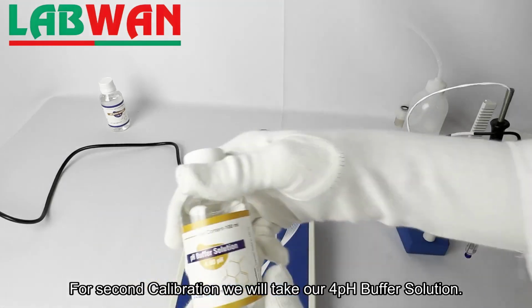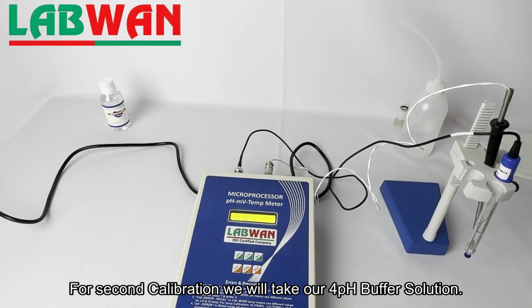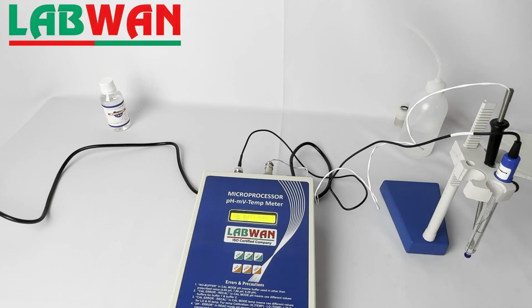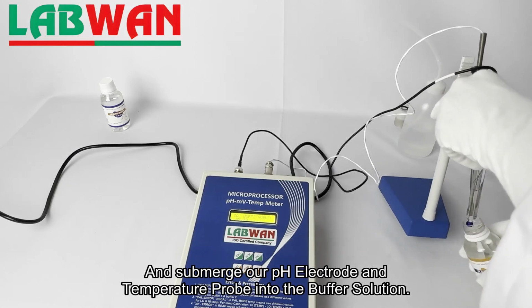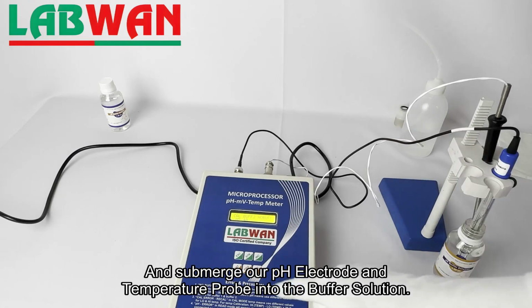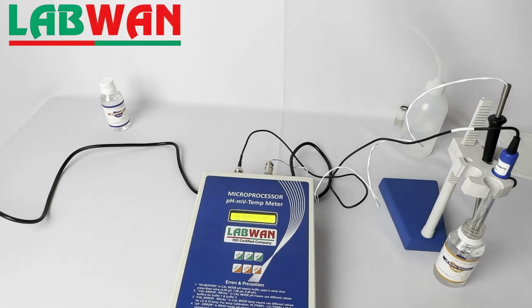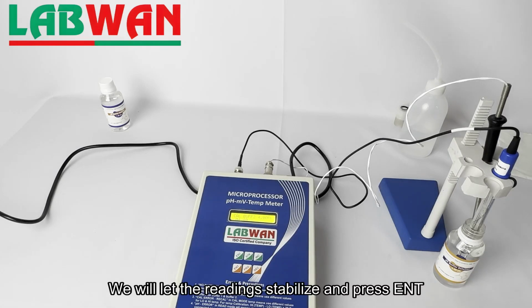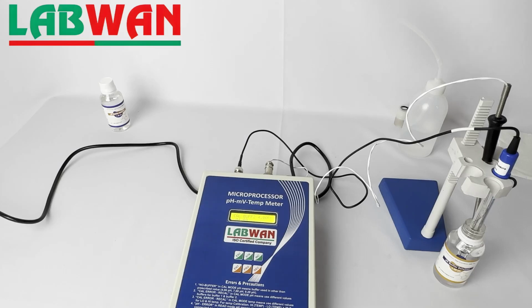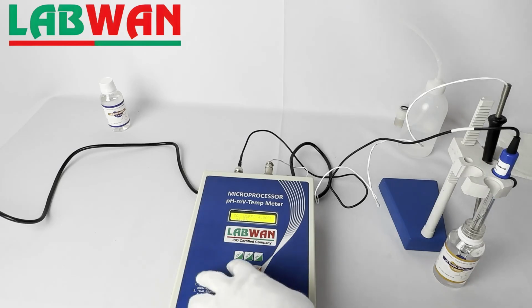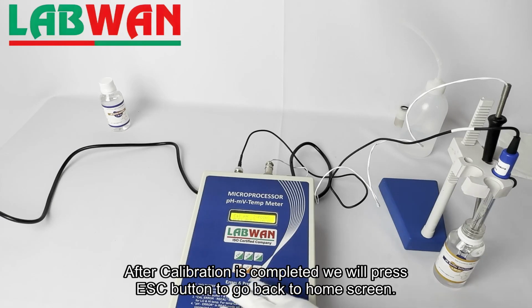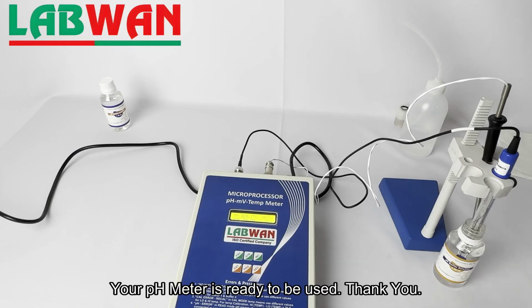For second calibration we will take our 4 pH buffer solution and submerge our pH electrode and temperature probe into the buffer solution. We will let the readings stabilize and press ENT. After calibration is completed we will press Escape button to go back to home screen. Your pH meter is ready to be used.